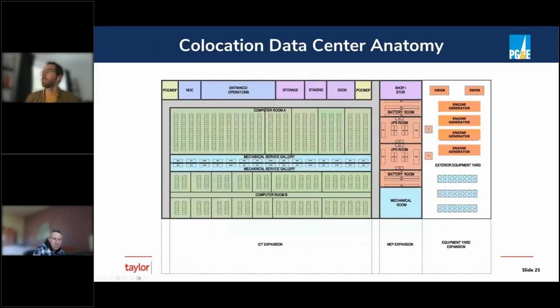The next example is for a colocation data center. Most of the parts and pieces are very similar. In this case, they're just arranged slightly differently. In the previous example, we had a flooded aisle design. This colocation data center is laid out with underfloor distribution. So you don't, for instance, see a bunch of air handlers plugged into the side of the building. And you also see in this case that the electrical rooms are not staged immediately adjacent to the computer rooms.